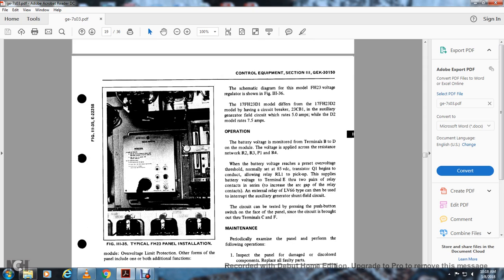The schematic diagram of the model of the FH23 voltage regulator is shown in figure 336. The 17FH23D1 module differs from the 17FH23D2. The module has a circuit breaker, 23CB1, in the auxiliary generator field circuit, which is rated 5.0 amps, while the D2 module is rated at 7.5 amps. Operation.